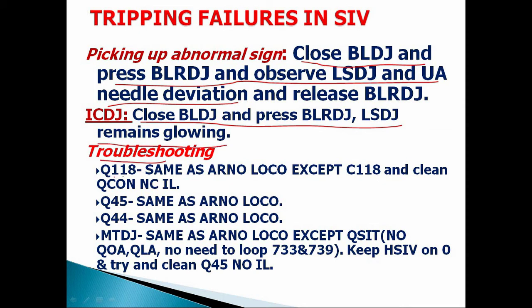Troubleshooting procedure is for Q118, it is same like Arno Loco except C118. There is no C118 contactor. C118 NC interlock need not to be checked, and clean the interlocks of QCon normally closed interlock which is provided on Q118 branch. So remaining part is same, manual operation or wedging is same.